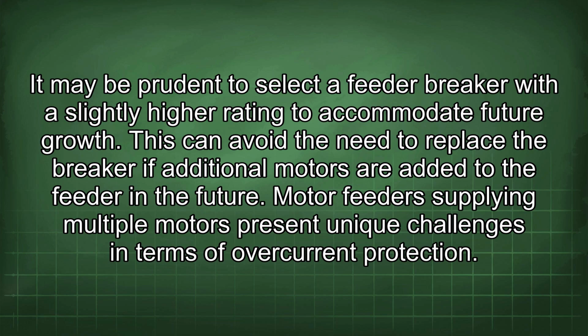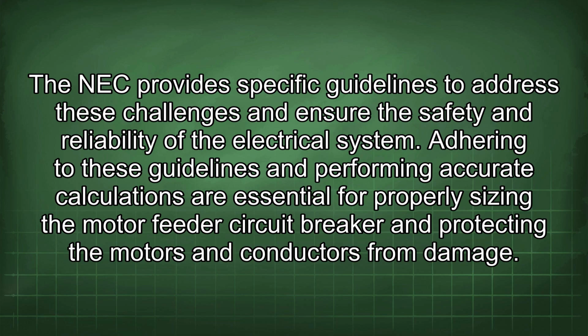This can avoid the need to replace the breaker if additional motors are added to the feeder in the future. Motor feeders supplying multiple motors present unique challenges in terms of overcurrent protection. The NEC provides specific guidelines to address these challenges and ensure the safety and reliability of the electrical system. Adhering to these guidelines and performing accurate calculations are essential for properly sizing the motor feeder circuit breaker and protecting the motors and conductors from damage.